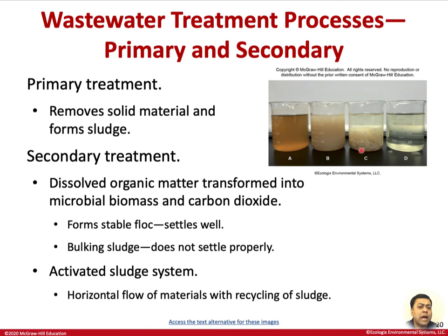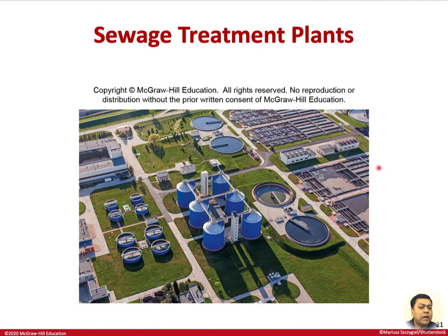So this just gives you an idea of how wastewater is actually treated. So let's take a look at the industrial scale, what happens in a typical sewage treatment plant. Just giving an overview, when all these sewer systems bring the material to these plants, usually there are some coarse filters. These filters, like 14, 15 millimeter fine mesh, filter out large plastics and debris so that there is no clog downstream.